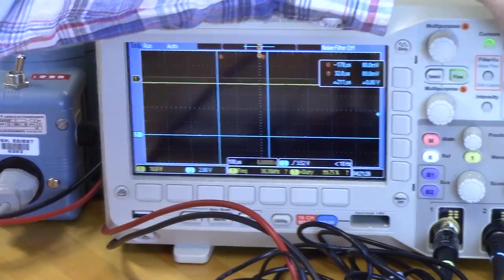For channel 1, we're going to change our vertical scale so that it'll pick up 60 hertz. Right now it's set for 10 volts per division; we want to set that for 2 volts per division. Okay, and let's set our triggering source on channel 1 so that it holds still on the screen and doesn't give us a headache.